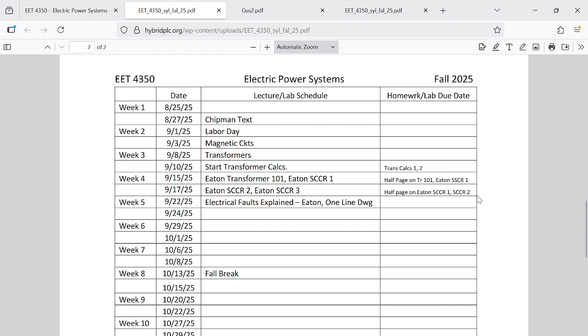Then the short circuit current rating, their full SCCR series, SCCR 1, SCCR 2, and SCCR 3. That should say a 2 and that should say a 3. By the time you get done with that, you should pretty much know how to do a short circuit current rating, a generalized one. Write it up to know how to calculate one, and to feel pretty confident that you could put that number on the front of a panel. So I want you to know what it stands for and how to calculate it.